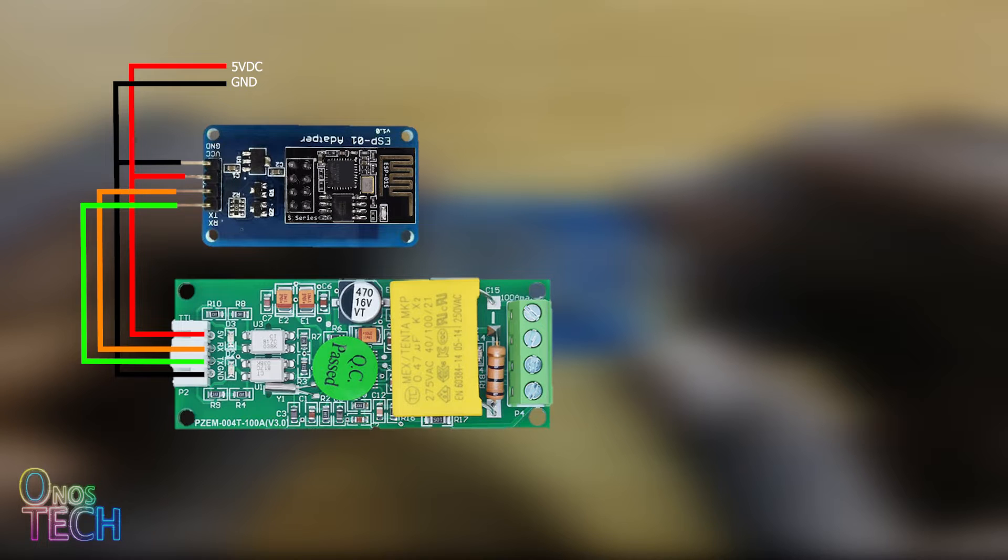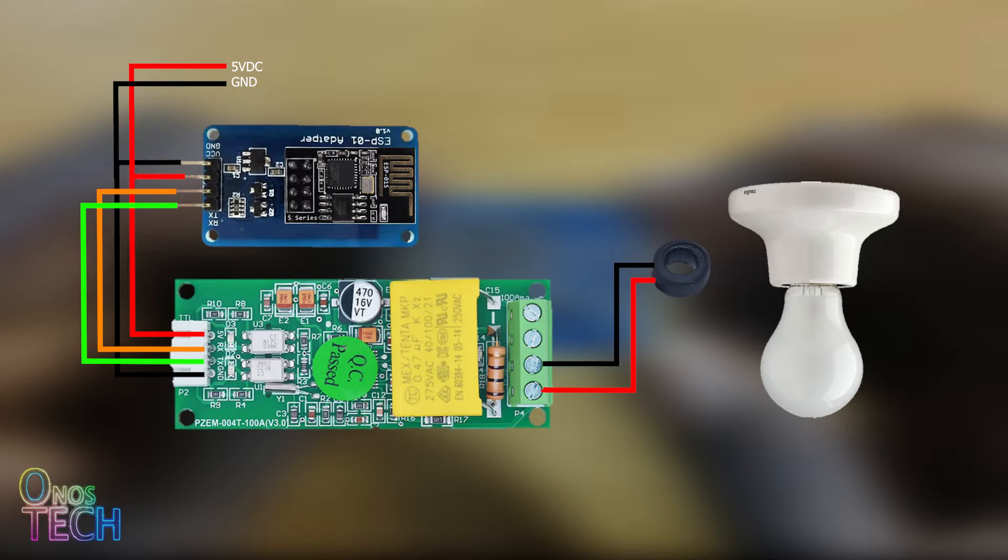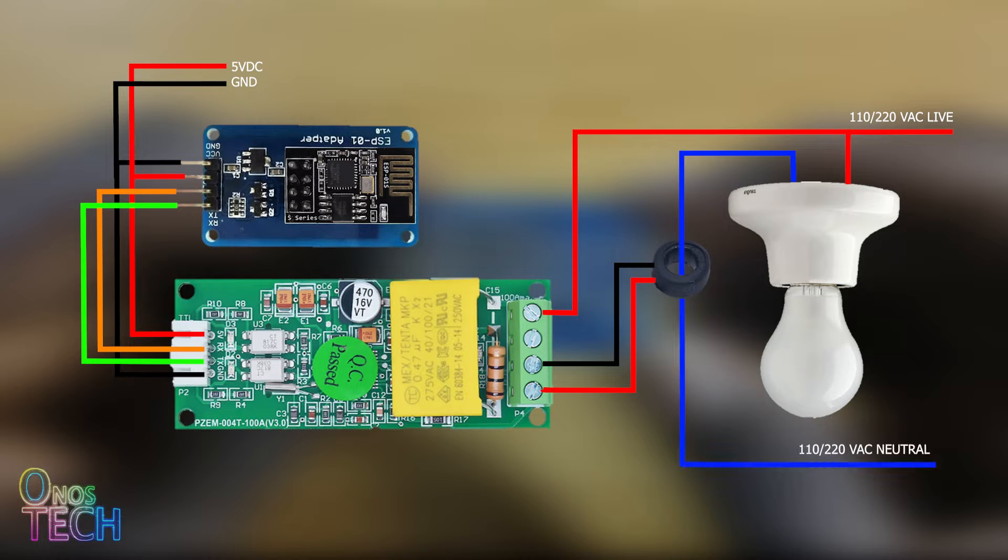My model type measures up to 100A of current with a current transformer connected to these inputs. The AC power supply line goes to the electrical loads to be measured and to this input of the model, and from the load through the current transformer to the neutral line as well as this other input of the model.